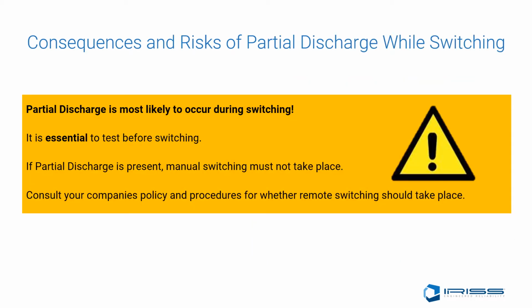The consequences and risks of partial discharge are pretty wide and varied. Partial discharge is most likely to occur during switching. It is essential to test before the switching process is engaged. If partial discharge is present, manually switching must not take place. Consult your company's policy and procedures for whether remote switching should take place in this situation.